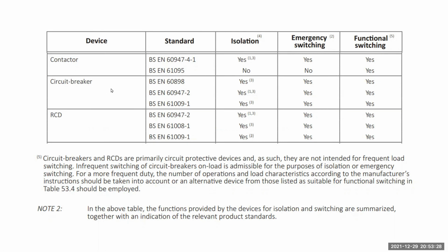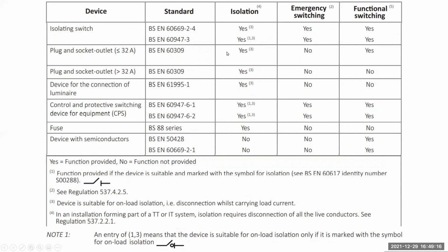So here we have circuit breakers to 60898, RCBO to 61009, and if we look, obviously they're applicable for isolation, emergency switching and functional switching. But the thing I want to draw your attention to here is that they are primarily circuit protective devices, and as such they are not intended for frequent load switching. Basically it suggests here that you should find alternative devices from those listed above. And this is the rest of the table.